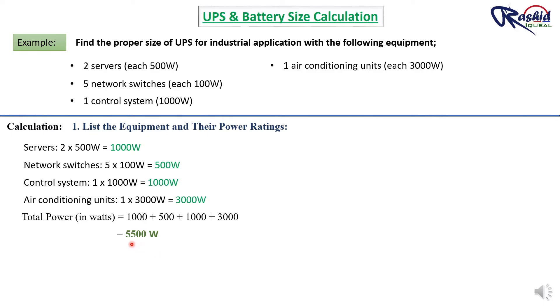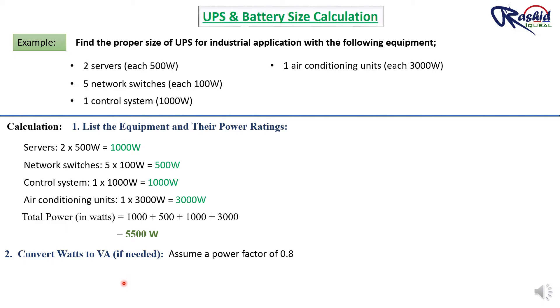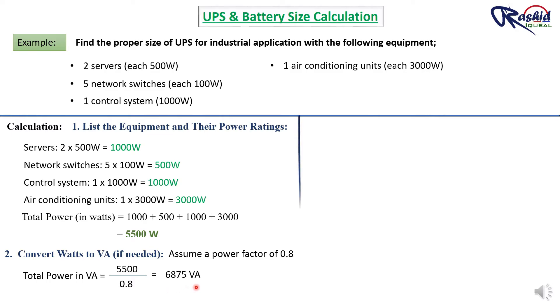For UPS calculation we require power in VA, not in Watts, so we convert. Assuming a power factor of 0.8, total power in VA equals 5500 divided by 0.8, which gives us 6875 VA.